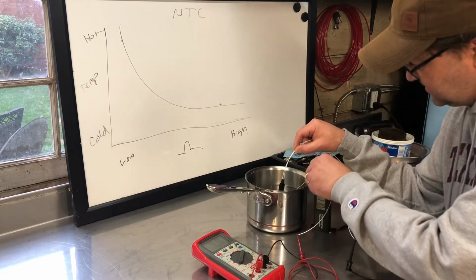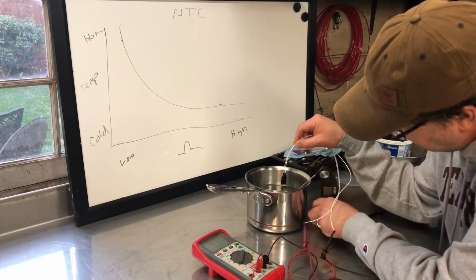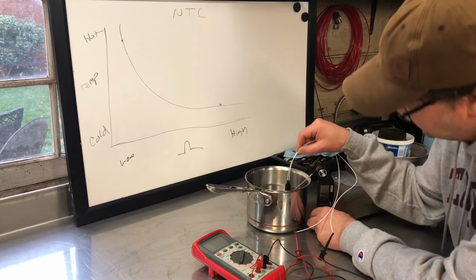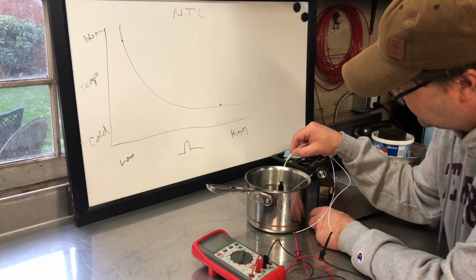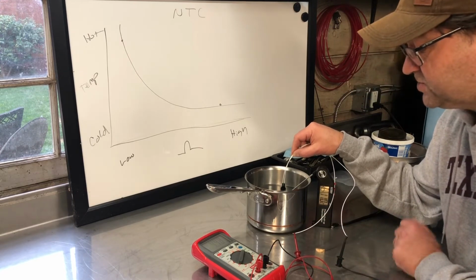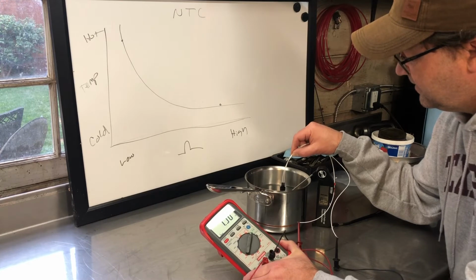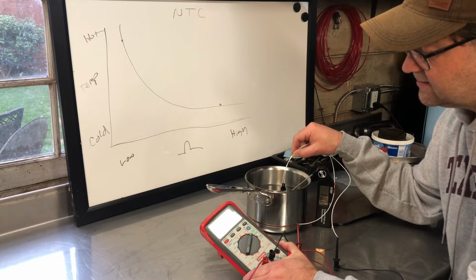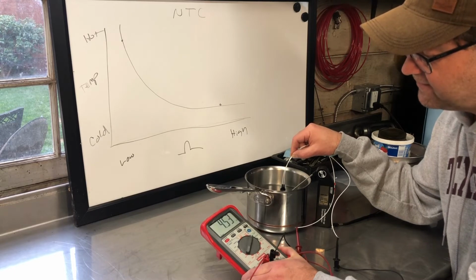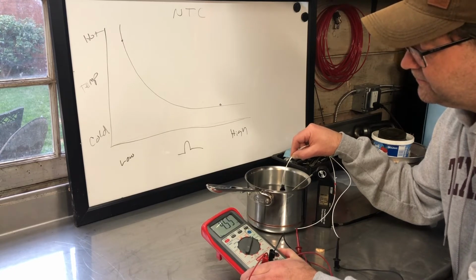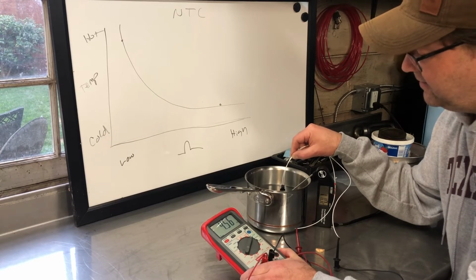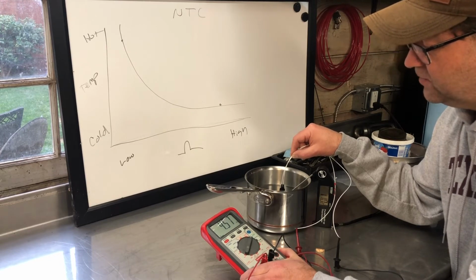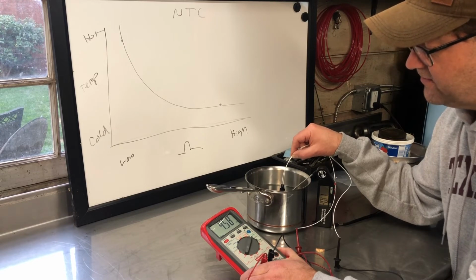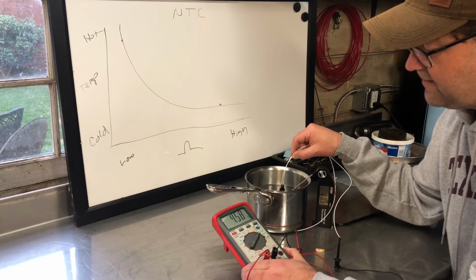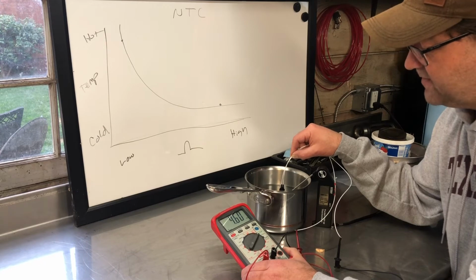But you can see that the temperature has settled at about 11.0 degrees Celsius. I'm watching the multimeter over here, and it's still moving, at 4.5 kiloohms. You can tell the temperature sensor is still cooling off because the resistance is still going up. At some point, the resistance will stop going up and level off and start going back down, because the water is going to start warming up as it's sitting out here.